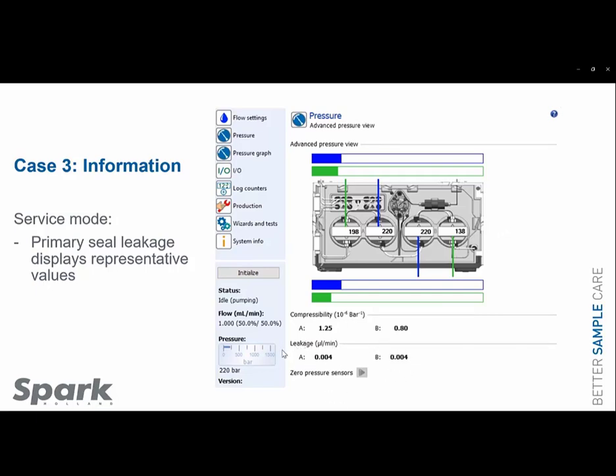This leakage value is a value for checking the primary high pressure seal. Primary pump head high pressure seal. So this is good. Well, we always say that typically this should be less than 5 microliters per minute. Actually, it doesn't matter how much this value is, because the primary pump head will only work a little bit harder to refill the secondary pump head, because that's what it's doing. But anyway, these are very good results. So there's nothing wrong with the primary high pressure seals.